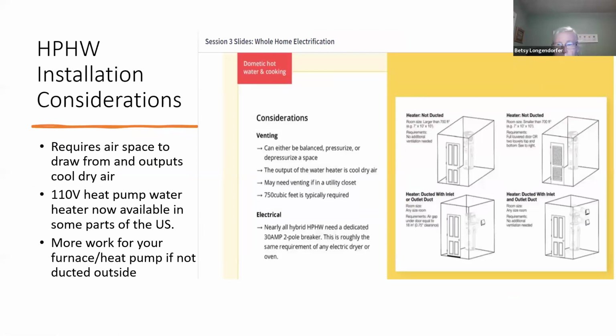These are different ways you can install a heat pump water heater. In some cases, as long as you have about 750 cubic feet of space, you don't need to vent it, but if you have less than that, you need to make sure it's vented elsewhere. They're also now coming out with 110 volt heat pump water heaters that can plug into a regular outlet. They're generally available in the southern US, but Rewiring America expects they'll be available in other parts of the US soon.